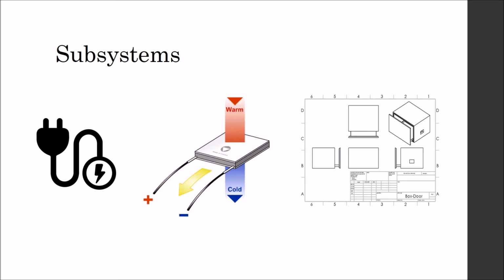Finally, we have the housing of the device itself. This is designed by the mechanical engineering students. It protects the device from the environment and outside light. The housing also allows for swapping the scintillator, so a user can use materials suited for their application.